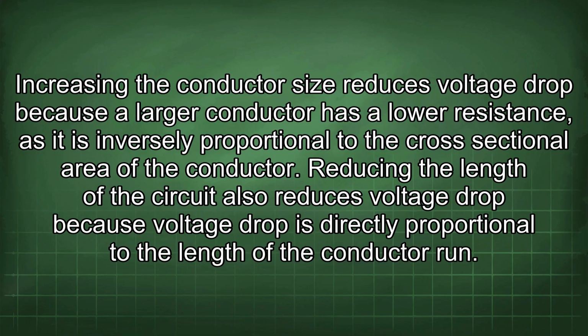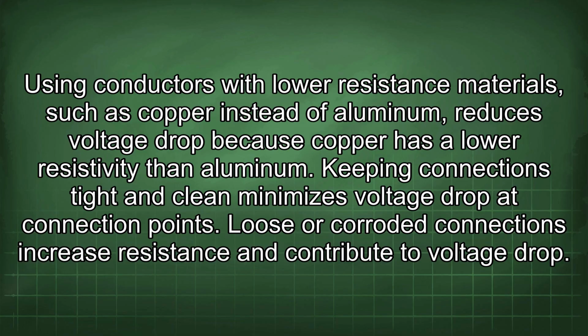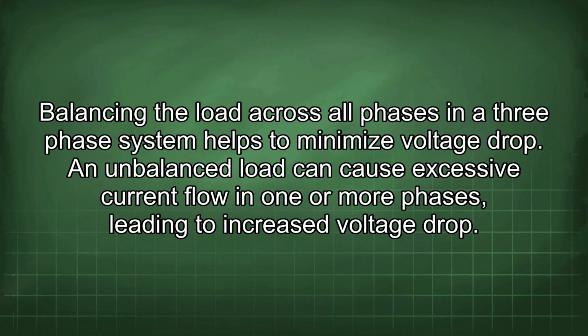Reducing the length of the circuit also reduces voltage drop because voltage drop is directly proportional to the length of the conductor run. Using conductors with lower resistance materials, such as copper instead of aluminum, reduces voltage drop because copper has a lower resistivity than aluminum. Keeping connections tight and clean minimizes voltage drop at connection points. Loose or corroded connections increase resistance and contribute to voltage drop. Balancing the load across all phases in a 3-phase system helps to minimize voltage drop. An unbalanced load can cause excessive current flow in one or more phases, leading to increased voltage drop.